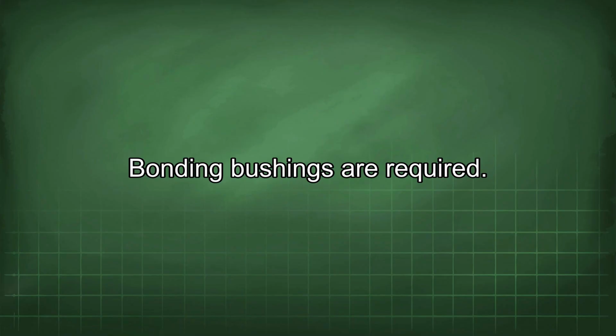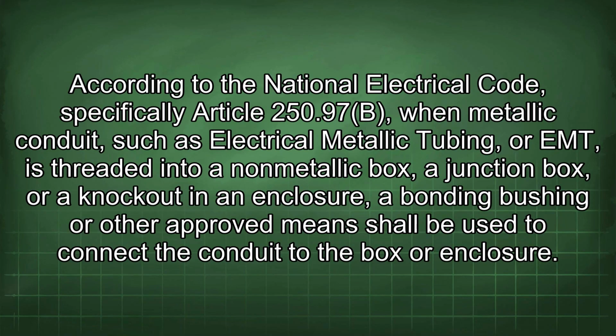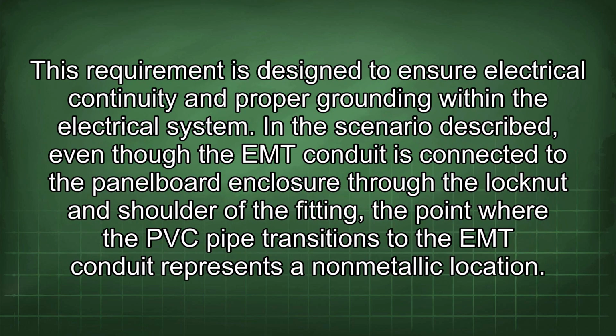Bonding bushings are required. According to the National Electrical Code, specifically Article 250.97(B), when metallic conduit, such as electrical metallic tubing, or EMT, is threaded into a non-metallic box, a junction box, or a knockout in an enclosure, a bonding bushing or other approved means shall be used to connect the conduit to the box or enclosure. This requirement is designed to ensure electrical continuity and proper grounding within the electrical system.